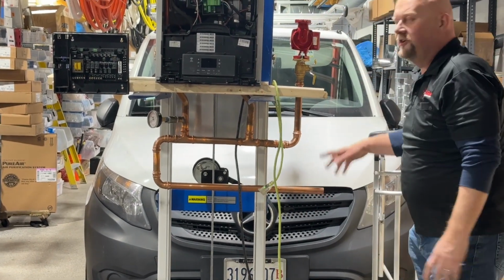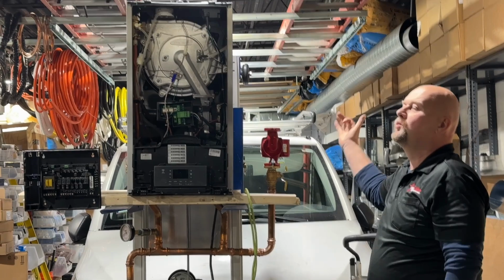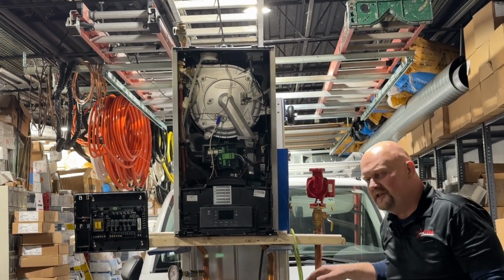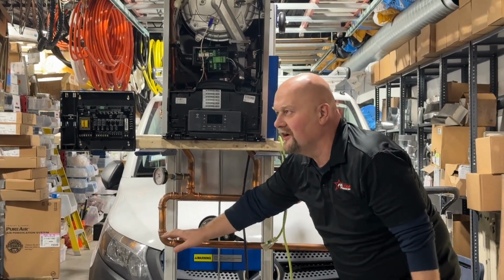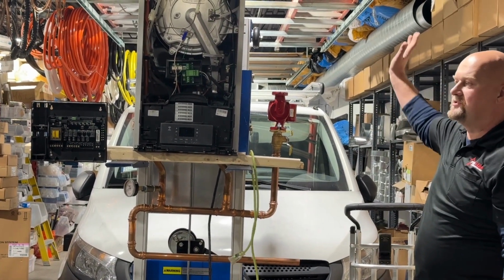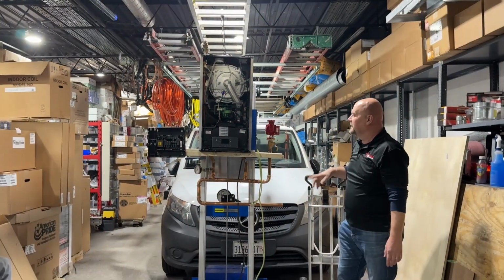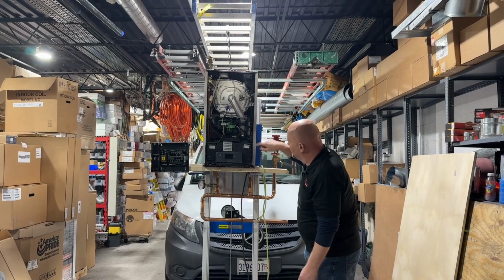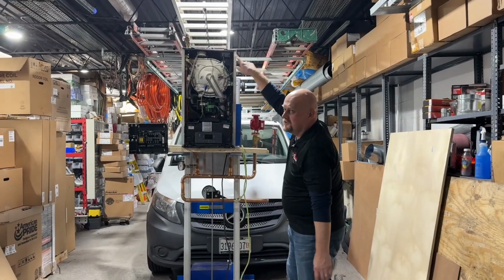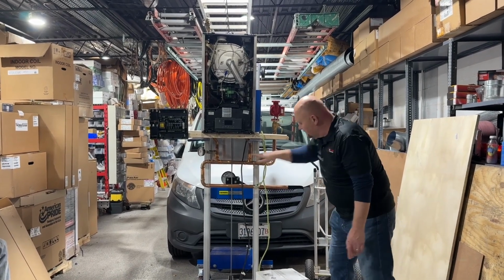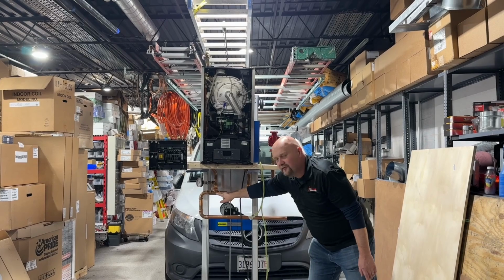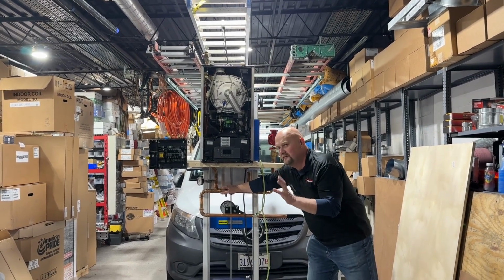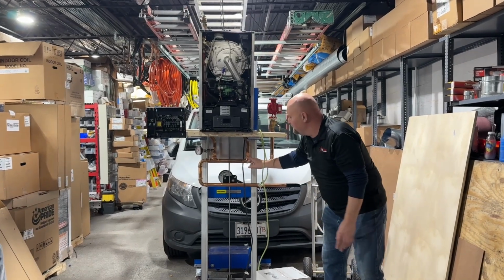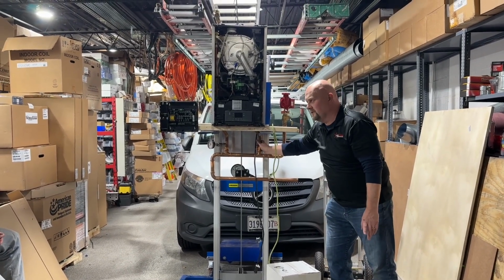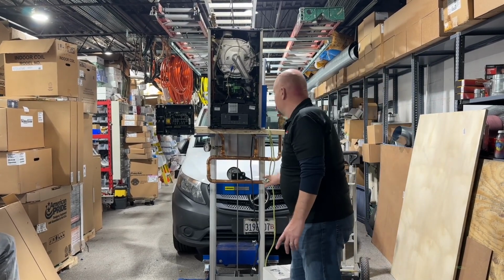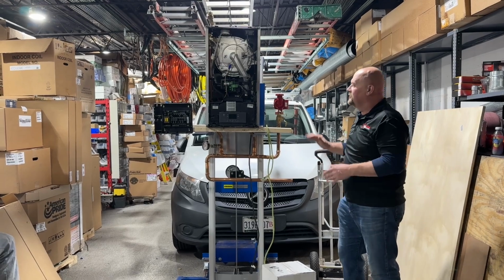Bear in mind, as the boiler keeps working, the water keeps coming back warmer and warmer from the radiators. At some point, you have 160-degree water coming back in, mixing with this 180, and you're coming up at 175, right? Because as the water comes back warmer, the mix affects it, makes it warm. So again, this is very important to understand. The pump inside does this circle. The pump in here does this circle. And they mix through this, and they refer to this as a close set of T's. T's that are close together. That's because this is the mixing point of the water. You understand, Rich? Good. So that part is hard to understand, but once you get it, it makes sense to you. You always have two pumps, right?